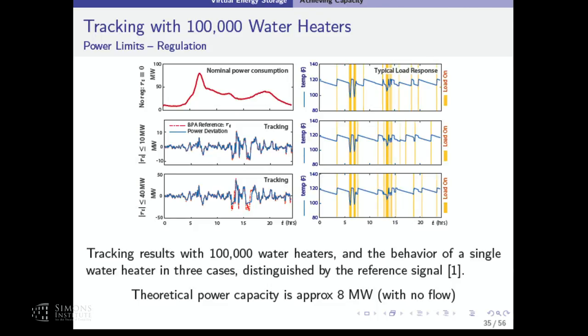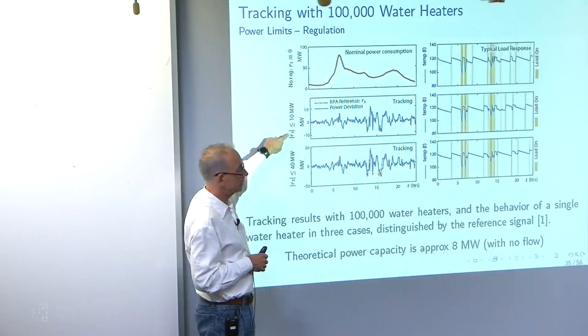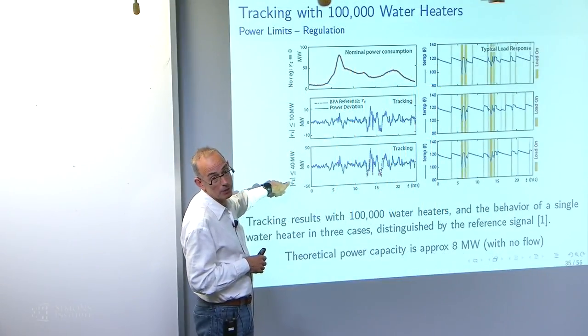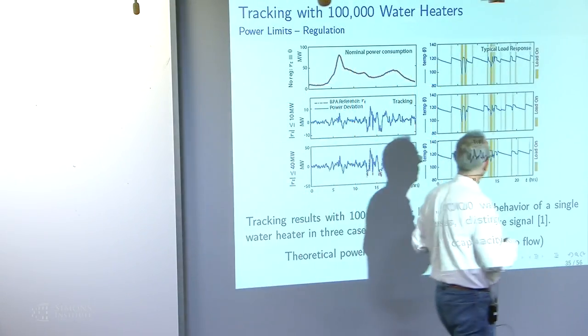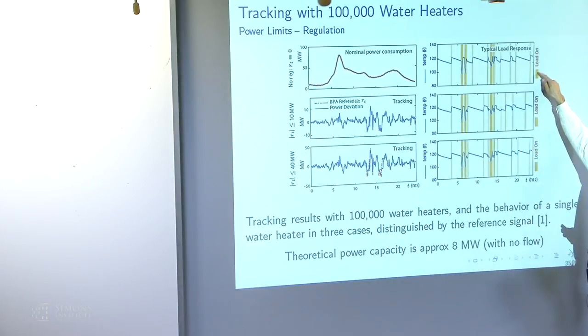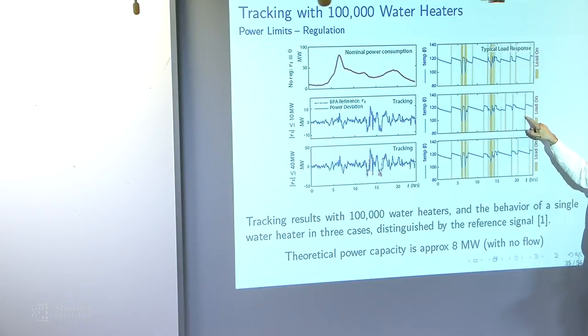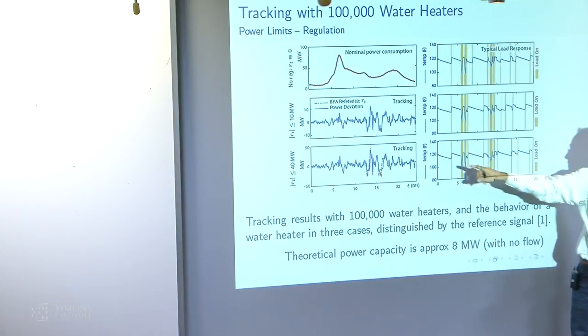In terms of achieving capacity, briefly, here's what happens with a particular control strategy: here's no reference signal to 100,000 water heaters, here's one scaled to plus or minus 10 megawatts, and here's one scaled to plus or minus 40 megawatts. Here's one of the loads taken arbitrarily, showing how it behaves normally with no interference, when the ensemble is following a regulation signal, and when it's being abused, because this wasn't feasible.